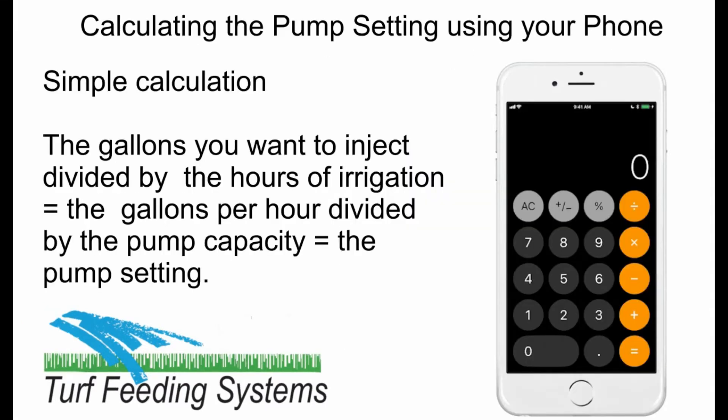The calculation is simple: the gallons you want to inject divided by the hours of irrigation equals the gallons per hour of injection, divided by the pump capacity equals the pump setting.